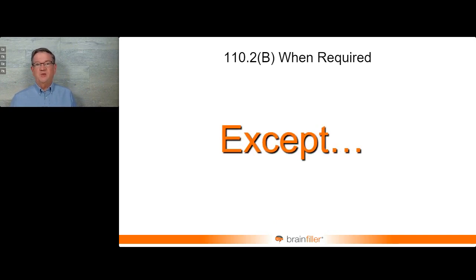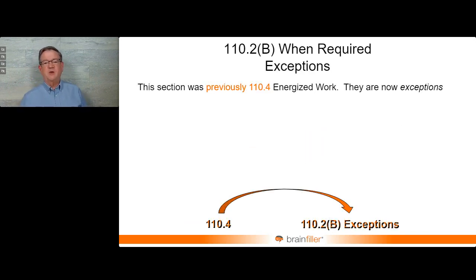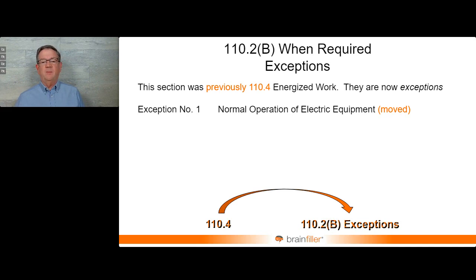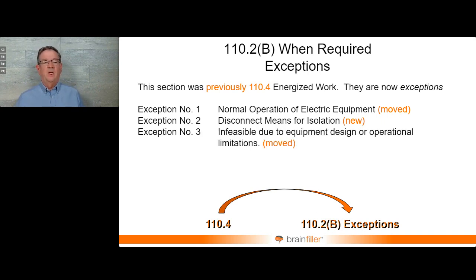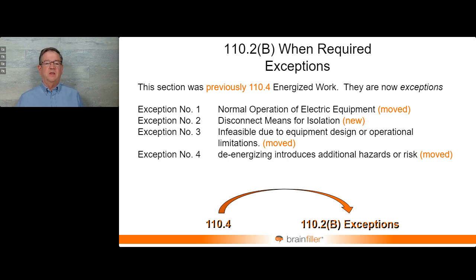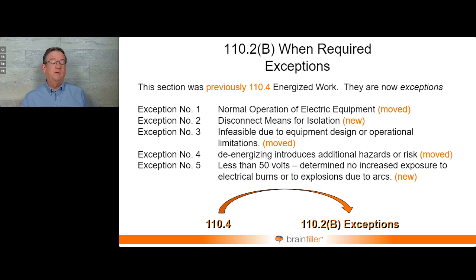So in general, you establish an electrically safe work condition, but there are exceptions. And many of the exceptions already existed. They were just relocated. But a couple of exceptions are new. Normal operation of electric equipment, that was there. It was relocated. Disconnect means of isolation for isolation, that's new. Infeasible, that's been around, that was moved. If it increases or introduces a hazard, if de-energizing introduces an additional hazard, that's been moved. And less than 50 volts, except the less than 50 volts now has a reference that you have to make sure there's not sufficient energy that can cause burns or explosions due to arcs. So a little bit of a change there.